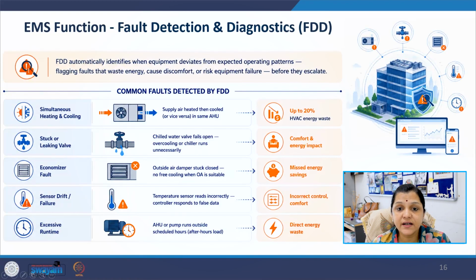Fault detection and diagnosis automatically identifies deviations from expected operating conditions. So one common fault is simultaneously heating and cooling within the same air handling system.